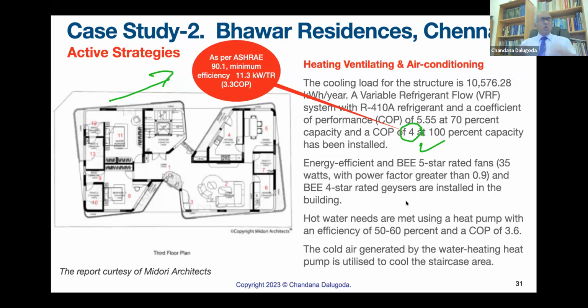Now, locally we buy, I will give you an example, things like DX split units. Efficiency, when you check, is 9 kilowatt per ton. The EER is 9. Now we'll have to bring it to 11.3 EER. EER should be 11.3. Now I have to correct this.